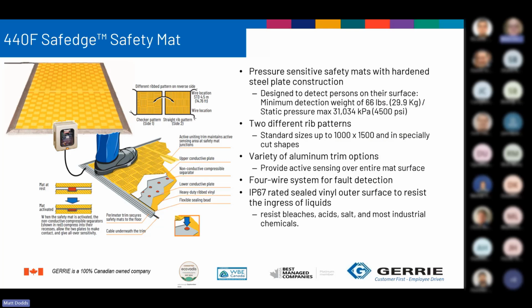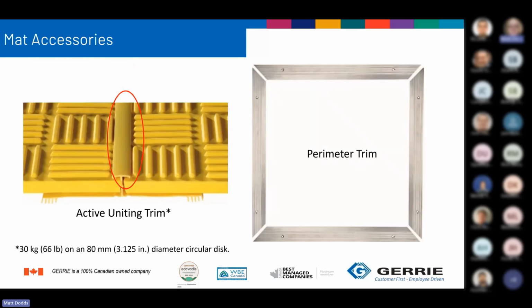So safety mats, what are they? They're just two mats or two plates of hardened steel with a separator designed to detect people. Minimum weight of 66 pounds with a static pressure of up to 4,500 pounds, so I could roll a forklift over one of these as well. Two different rib patterns, standard sizes up to 1,000 millimeters by 1,500 millimeters in a variety of shapes. There are some different trim options for holding these down, 4 wires for fault detection, and they have an IP67 rated vinyl outer surface, so again, resistant to bleaches, acids, salt, and most industrial chemicals.